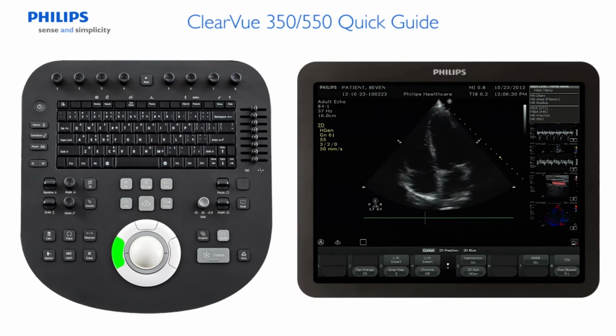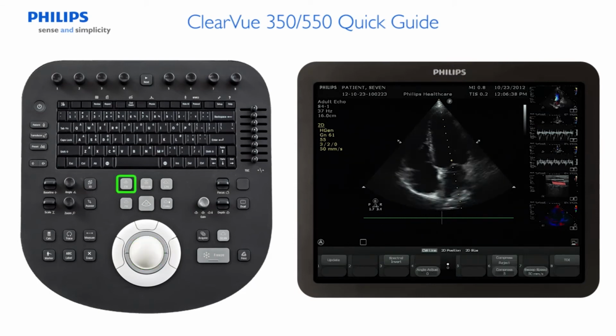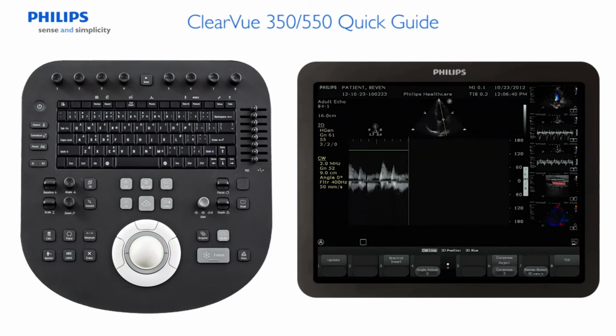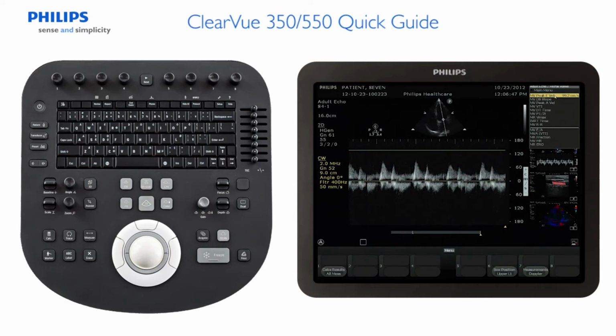Press the left trackball button to position the sample line cursor over the area of interest. Press the CW key to activate the Doppler spectral sweep. Press the freeze key to perform measurements. To perform Doppler calculations, follow the same procedure as pulsed wave Doppler measurements.